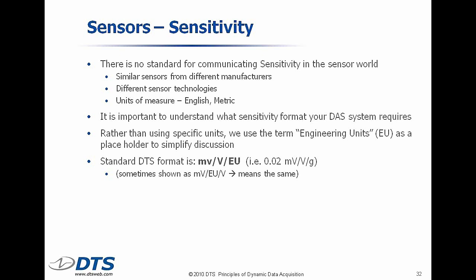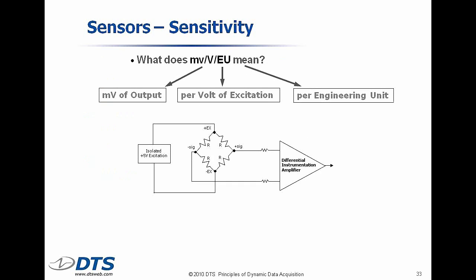Our standard format for sensitivity is millivolts per volt per engineering unit. We use the term engineering unit as a placeholder so we don't have to keep saying, was that pounds or Gs or newtons or inch pounds. So when we say engineering units, it's whatever you're measuring. So the standard input the DAS needs, and this applies to everybody, is how much output from the transducer do I get for each, say, volt of excitation I supply for how much force or load or Gs.